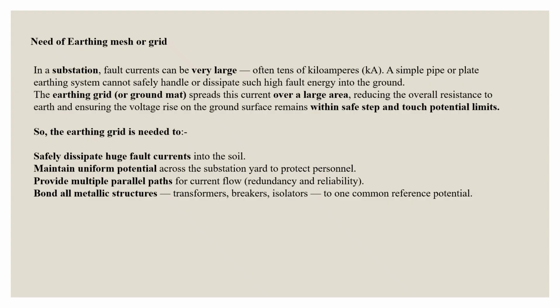So the earthing grid is needed to safely dissipate fault currents into the soil, to maintain uniform potential across the substation yard, to protect any person working there, to provide multiple parallel paths for current flow, and to bond all metallic structures like transformers, breakers, and isolators to one common reference potential.